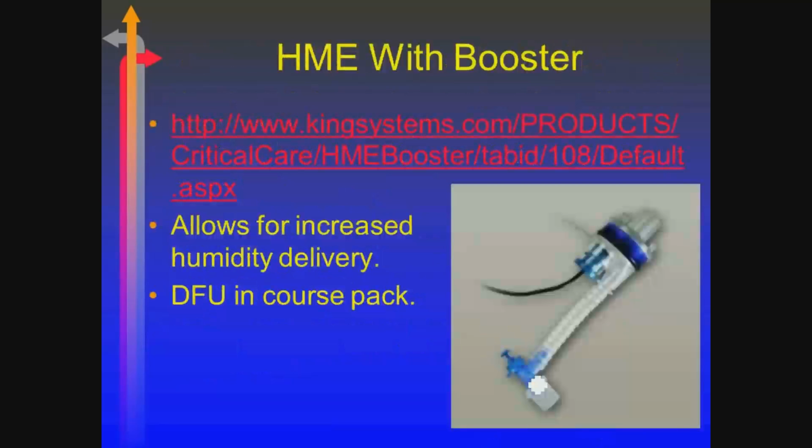Booster HME. Booster HME works, and you should have in your packet directions for use that explain how this works. But basically, this is a standard HME, or not a standard, but it can be used by itself as just an HME. It also has a small area, a small little heater. This is a heater. And this is a little drip chamber with an IV bag of water.